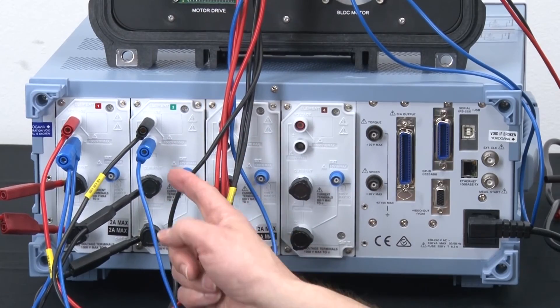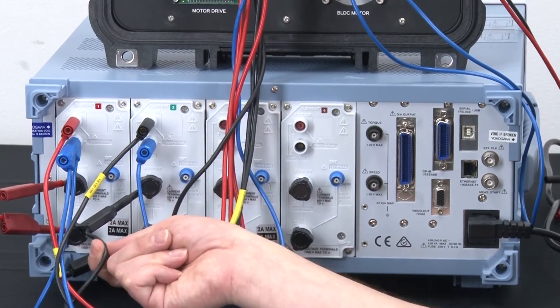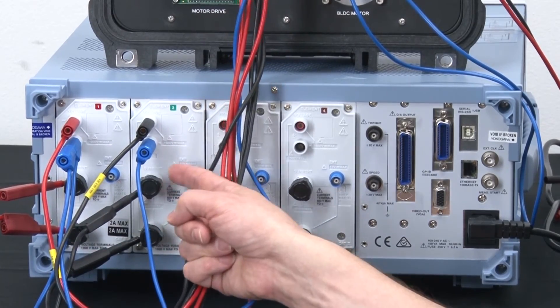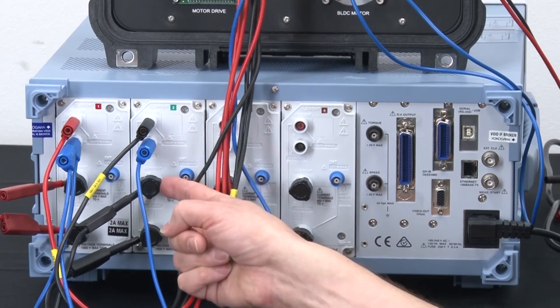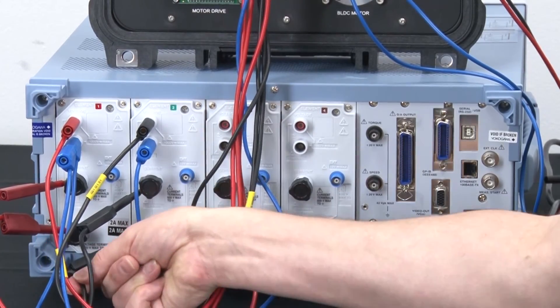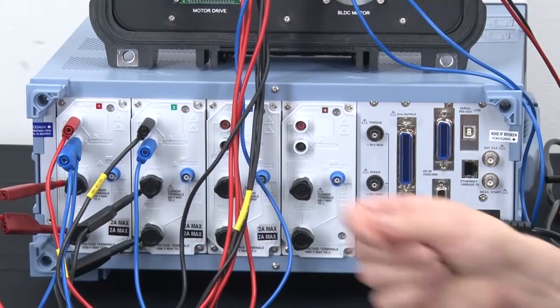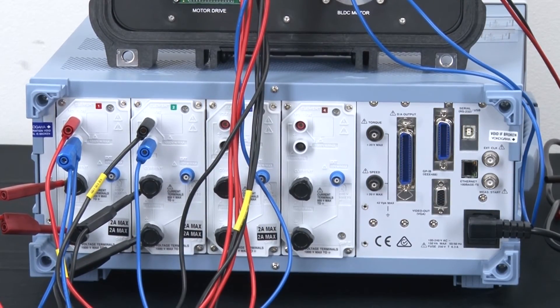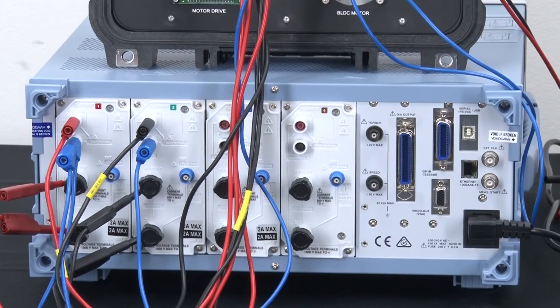Similarly, on wattmeter two, phase S comes from the drive. It's black. It passes through the top of the internal shunt or the current input on wattmeter two, passes out the bottom back to the motor. It's that simple. So let's do an easy or quick power measurement using the setup.